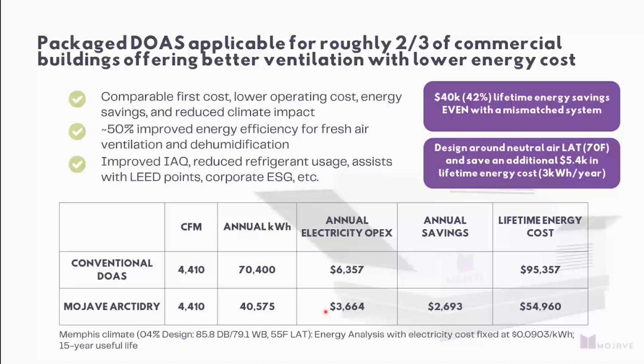And then I would also call out that in this particular case, the client wanted to see a 55-degree off cooling coil. If we had designed around Mojave originally with a 70-degree leaving air temp out of the unit, we would have been able to save an extra roughly $5,500 over the life cycle of the unit by leveraging the liquid desiccant to come off coil at a higher temperature than that 55 and downsizing the refrigeration circuit.